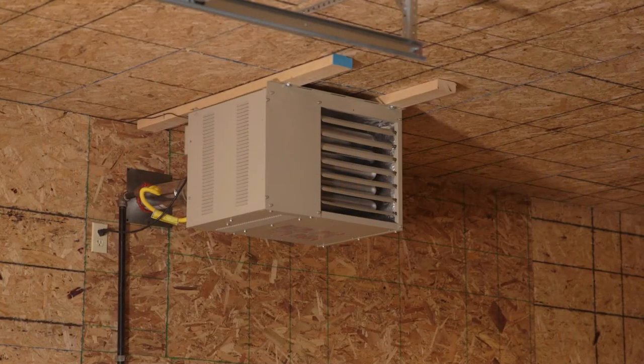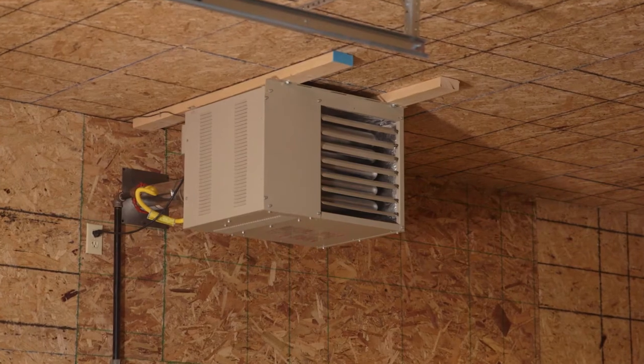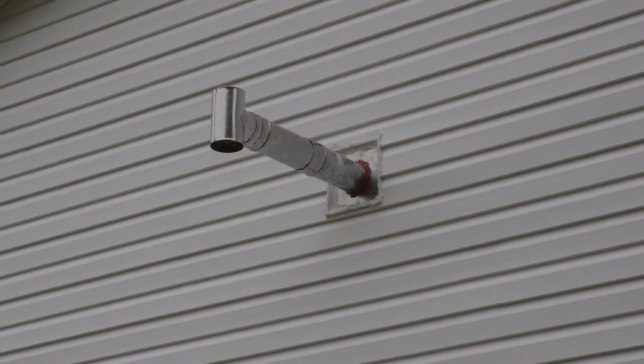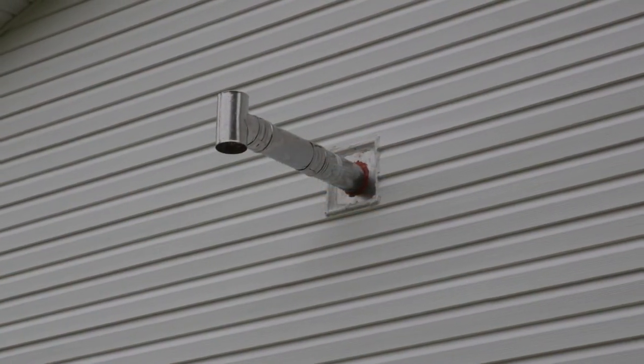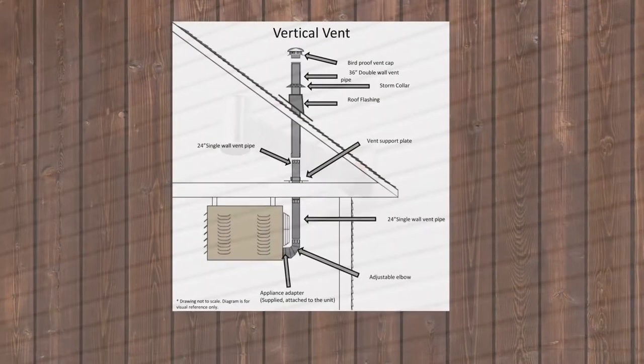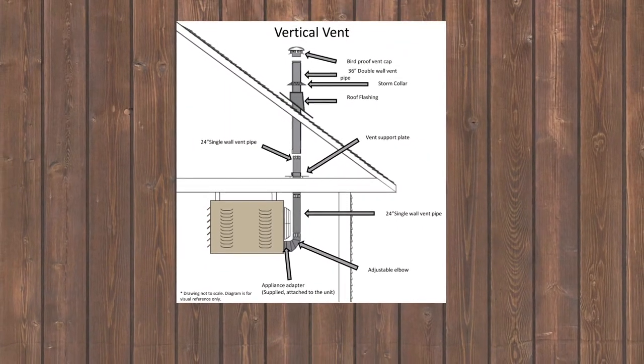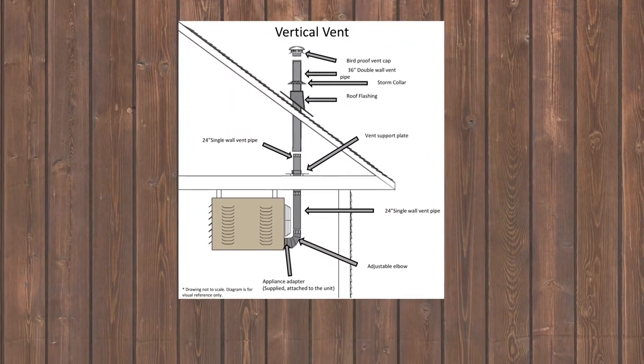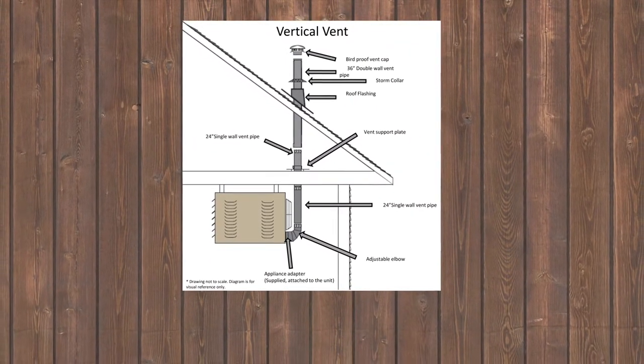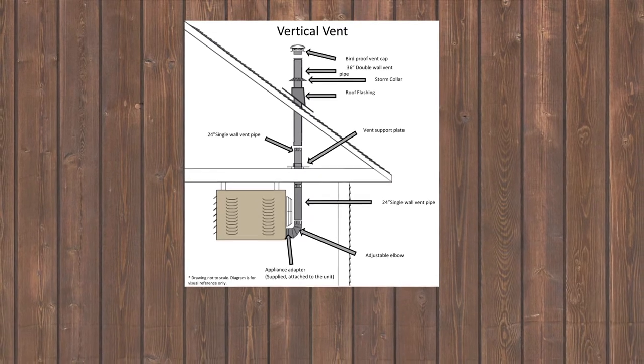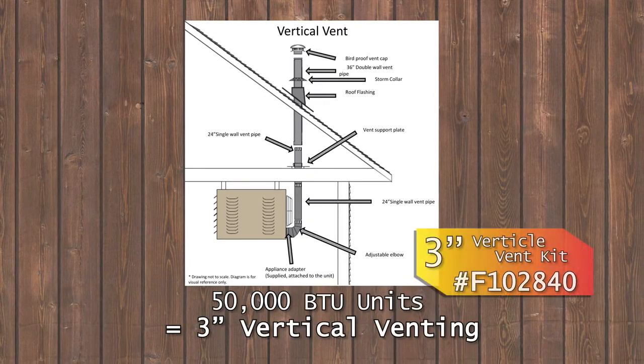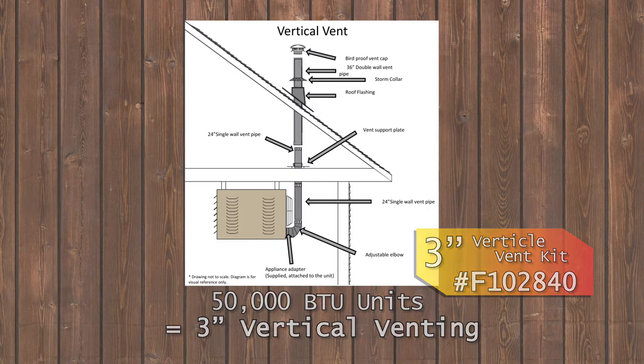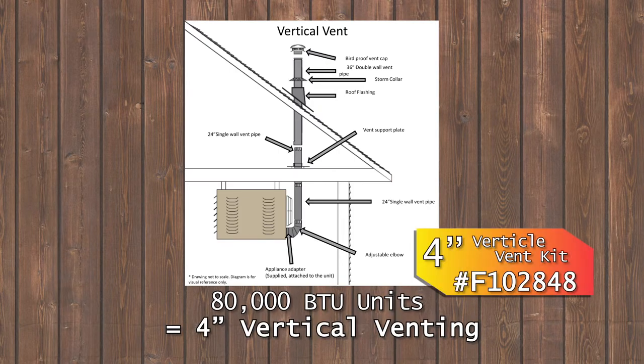Failure to comply will void certification of the unit. For venting, always follow local building codes. For vertical venting with metal vent pipe, all units are considered Category 1 appliances. 50,000 BTU units can use 3-inch vertical flue piping. 80,000 BTU units must use 4-inch vertical venting.